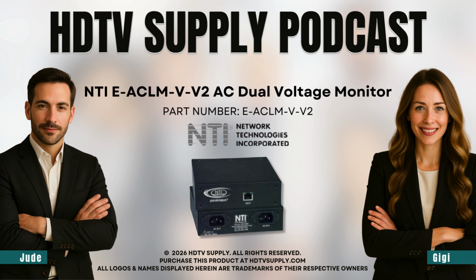Moving on to integration. How does this data get back to that main system? I'm seeing UL-certified IEC 320 C14 inlets and the RS-485 protocol. That sounds a little like jargon. Yeah, it does, but let's break it down. The C14 inlet is just that standard, tough, industrial-grade connector you see on most server equipment. Okay, so it's familiar hardware. Right. And RS-485 is just a communication protocol. It's used everywhere in industry because it's exceptionally reliable, especially over long distances or in electrically noisy places.